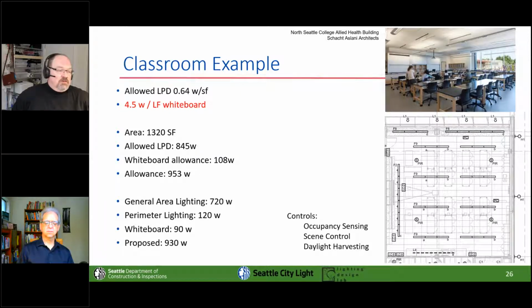So my allowance for a classroom is 0.64 watts per square foot, right? Plus the 4.5 watts per linear foot for the whiteboard. So my overall allowance, looking at both of those things, is 953 watts. So if I look at my general area lighting, well, that became 720 watts with LED, 120 watts of perimeter lighting, that's at the window wall there. Whiteboard is 90, my proposed is 930 watts. So again, this is just a quick example of how you can meet that.